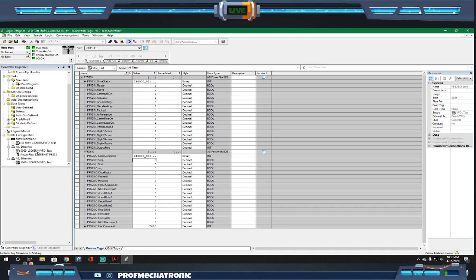Again, if you were to add more VFDs to your network, you would just follow the same procedures, right? You'd add another module. You'd obviously give it a different name. That module would fall underneath that Ethernet IP communications protocol. And because it would have a different name, it would have a different tag structure. So it'd be PF525_2, then it would just show PF525_2:O for your outputs or your inputs.